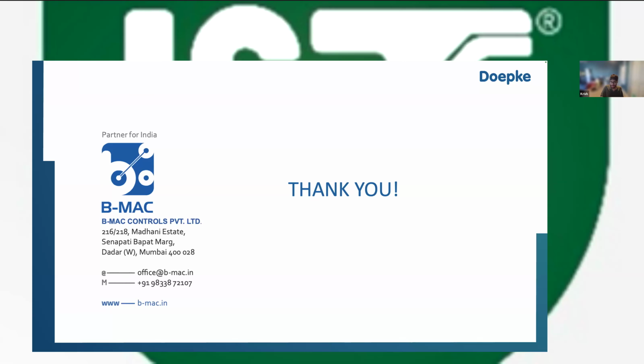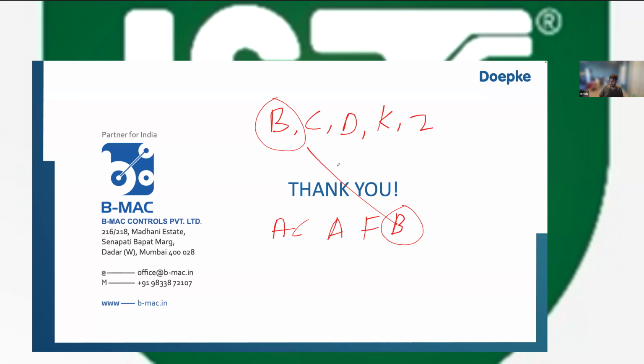What to tell the guys on site is: don't get confused between the Type B RCD and the Type B MCB. MCBs are also available in categories. For example, MCBs are available in B, C, D, and some have K and Z also. And RCDs are available in AC, A, F, and B. This B and this B have nothing to do with each other.